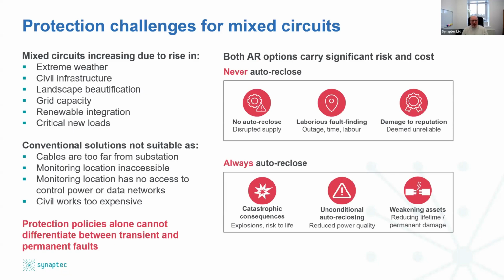Very often when we talk to our customers, we find either their policy is never to auto reclose if there are cable sections in the circuit, because if it always auto recloses, you risk accidentally reclosing on a cable section fault. That's a permanent fault. That's going to be very expensive and cause a lot of damage, because you're exposing assets a second time when you reclose to fault level currents. Or you're always reclosing. Either way, there is a challenge here, because it's a suboptimal solution.